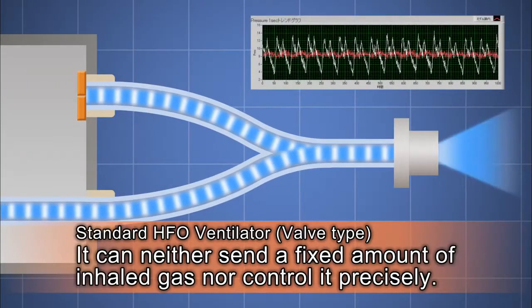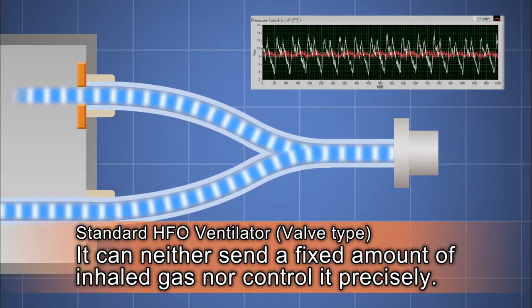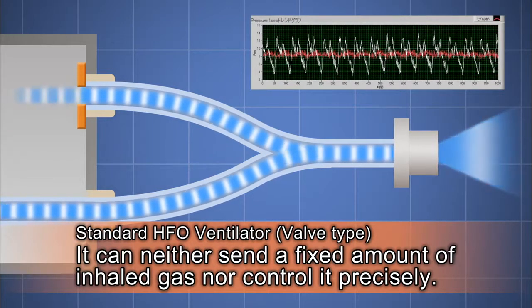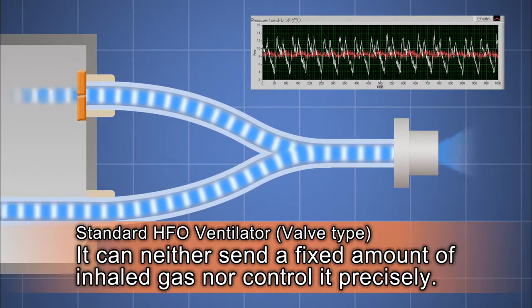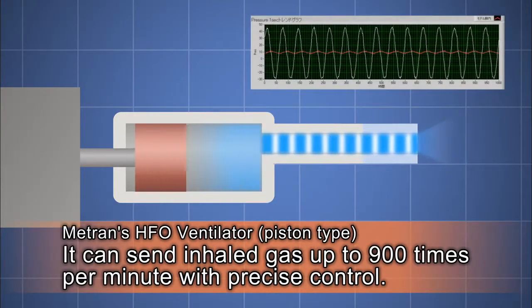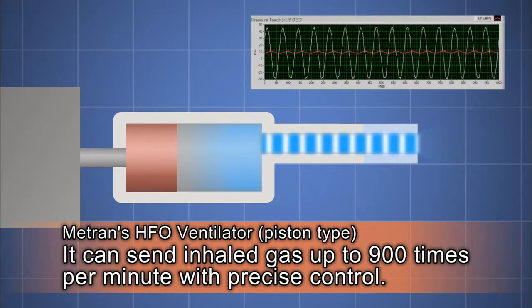Standard HFO ventilators send gas compressed by a bulb. That type of ventilator doesn't provide uniform gas volume, nor can they be precisely controlled. In contrast, Metran's ventilators are able to precisely control gas volume, thanks to a linear motor-driven piston.